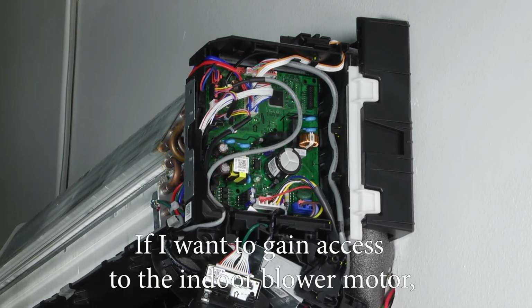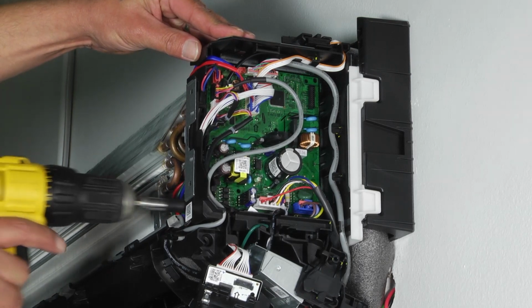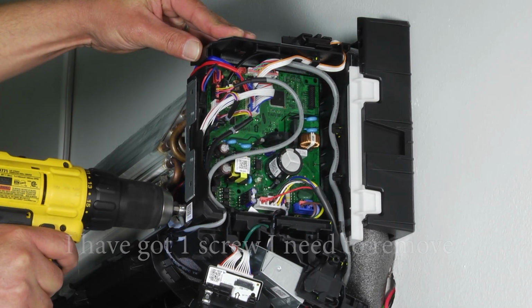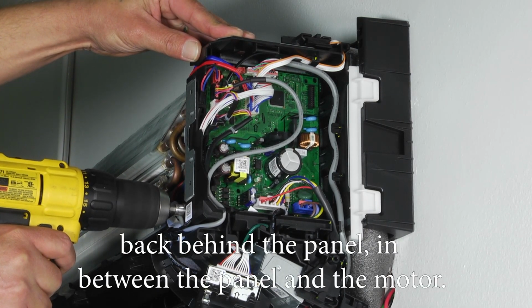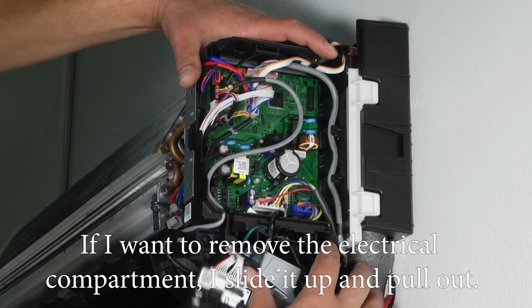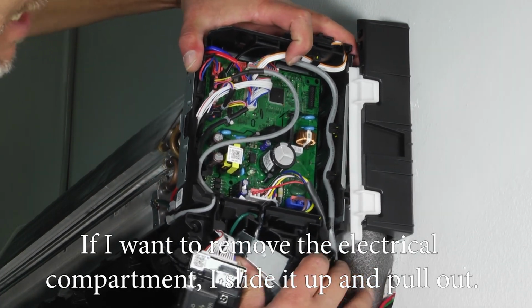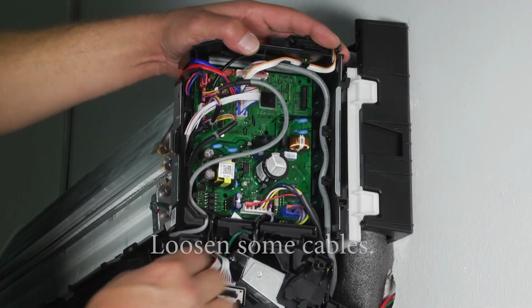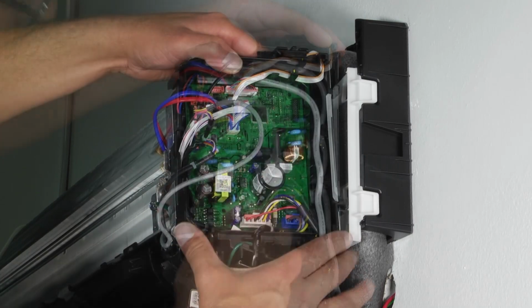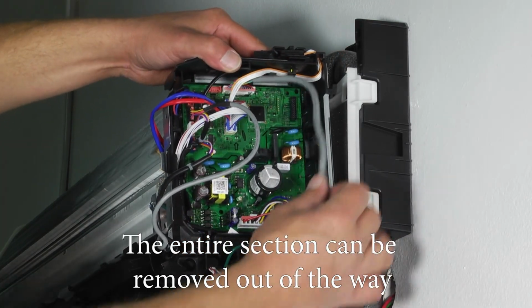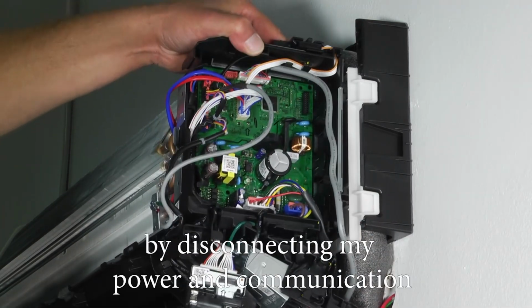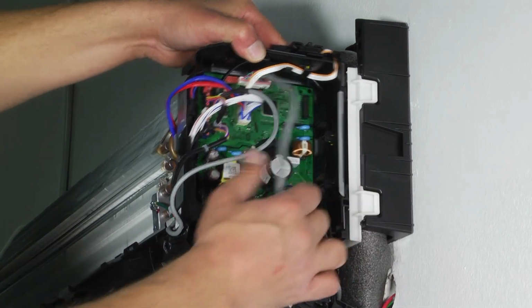If I want to gain access to the indoor blower motor, I've got 1 screw I need to remove back behind the panel, in between the panel and the motor. If I want to move the electrical compartment, I slide it up and pull out, loosen some cables. The entire section can be removed out of the way by disconnecting my power and communication and loosening some cables.